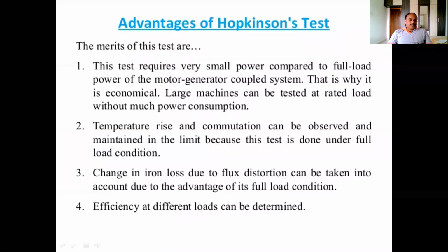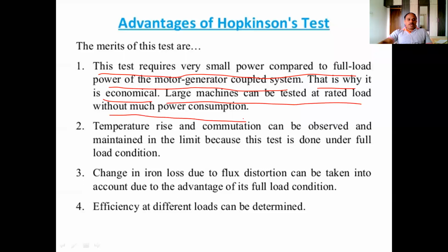The advantage of this test is that it requires very small power compared to the full load power of the motor generator coupled system. That is why it is economical. Large machines can be tested at rated load without much power consumption, because in this test the power consumed is only to meet the losses.